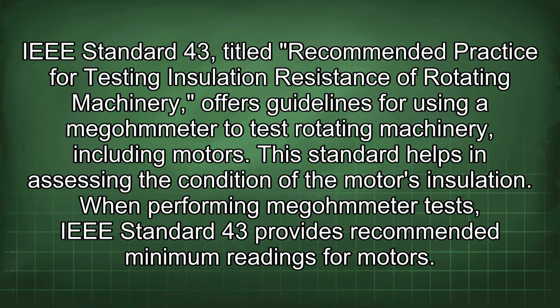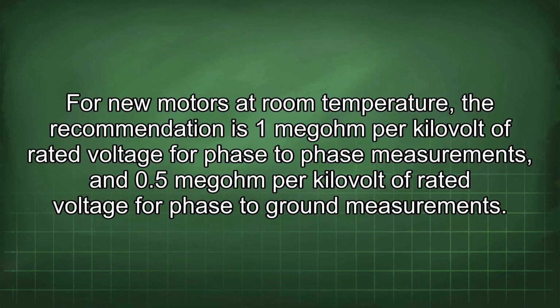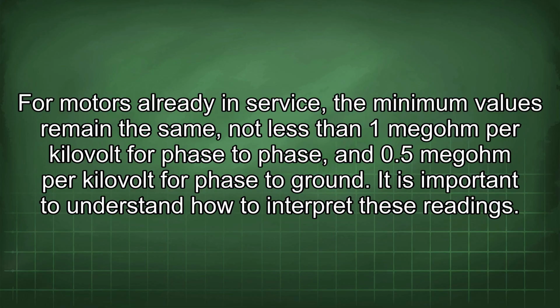When performing megohmmeter tests, IEEE Standard 43 provides recommended minimum readings for motors. For new motors at room temperature, the recommendation is 1 megohm per kilovolt of rated voltage for phase-to-phase measurements and 0.5 megohm per kilovolt of rated voltage for phase-to-ground measurements. For motors already in service, the minimum values remain the same, not less than 1 megohm per kilovolt for phase-to-phase and 0.5 megohm per kilovolt for phase-to-ground.